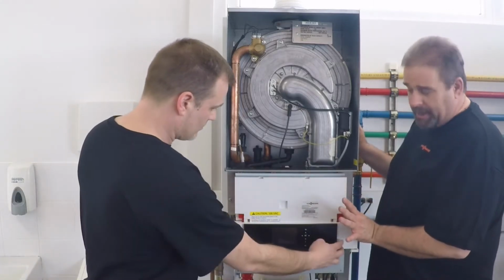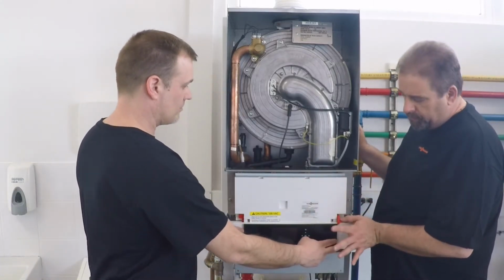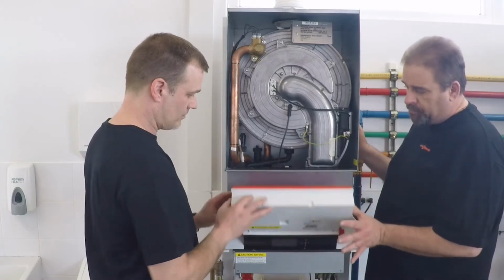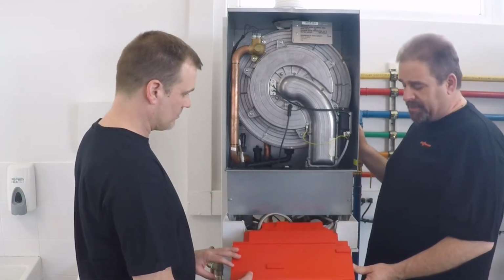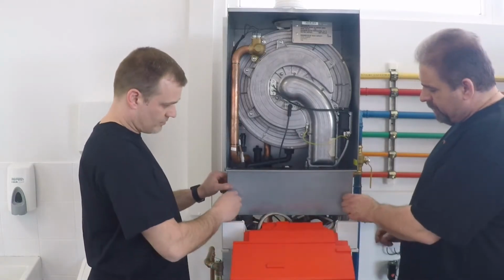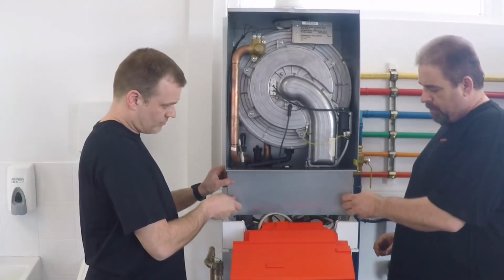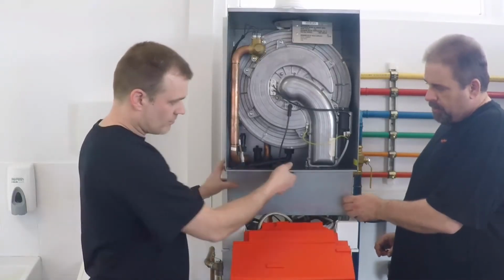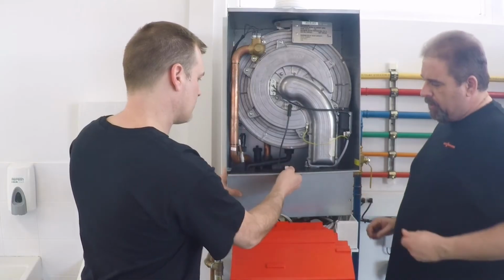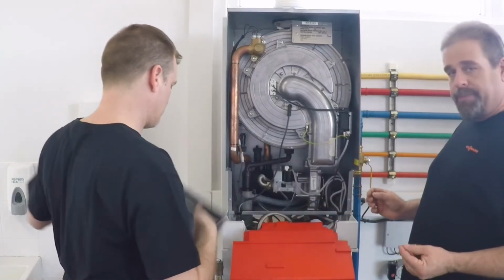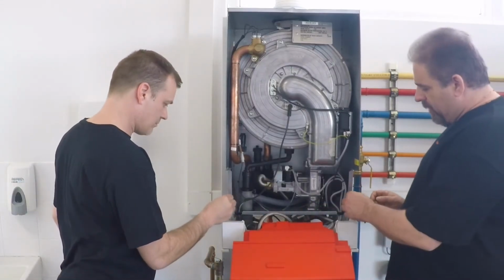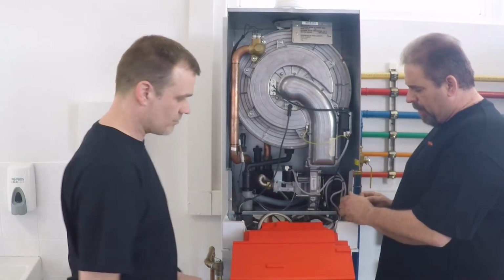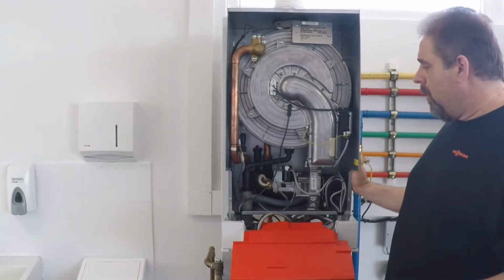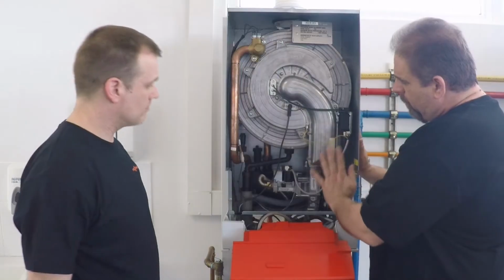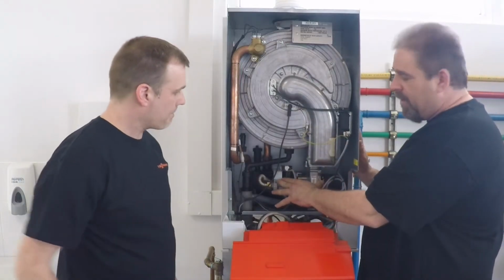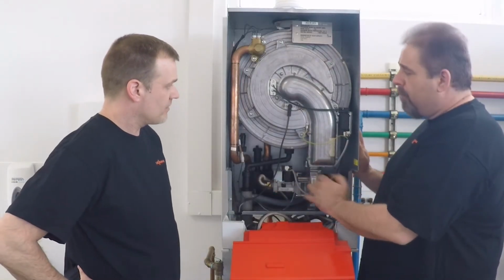So there's 2 red hinges here that we flip down. Control console comes out, slides down out of place. And then there's 2 nuts here that we remove for this panel to be removed. And then we want to reinstall the nuts on those studs so we don't drop them and lose them down the floor drain.